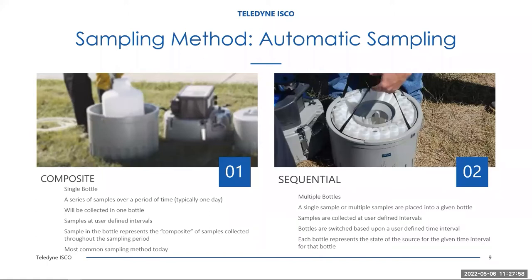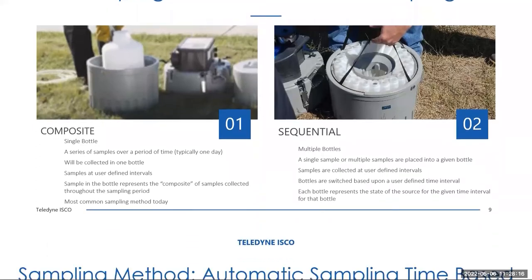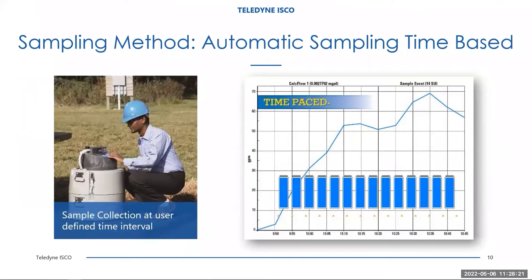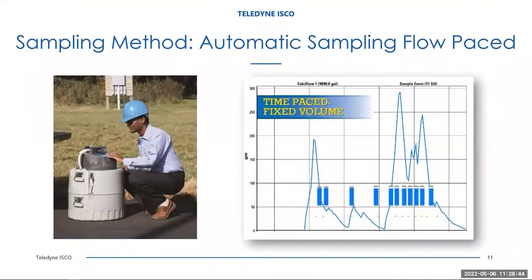It is also worth noting that we do have another sampling option — the vacuum sampler. However, for portable sampler applications, the peristaltic pump is the most appropriate option to select. This is an example of a time-paced program in a multiple-bottle sampler, where you can see that at regular intervals those samples were collected over that period of time. This would be an example of a flow-paced sampling routine where you can see that the intensity of sample collection is greater when flow is high, because we are pacing the sample based upon flow volume moving past this site over that period of time.